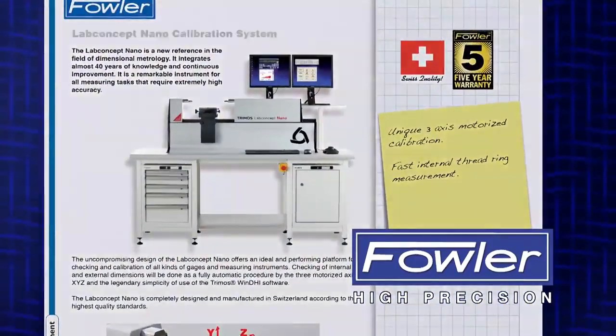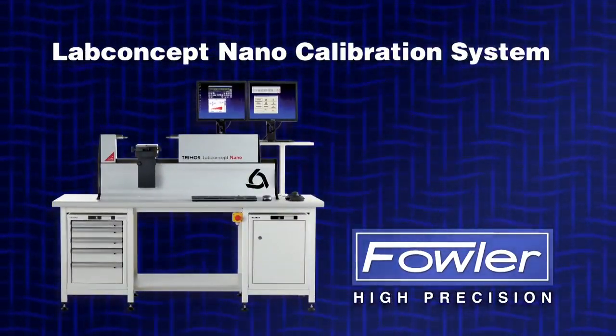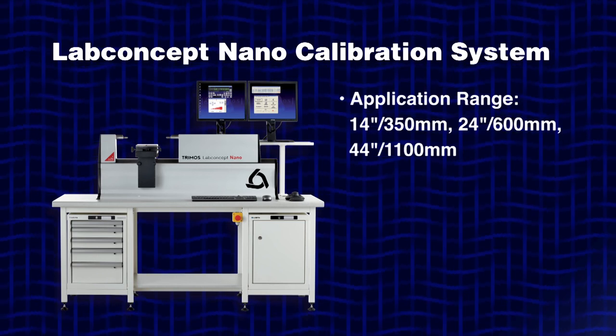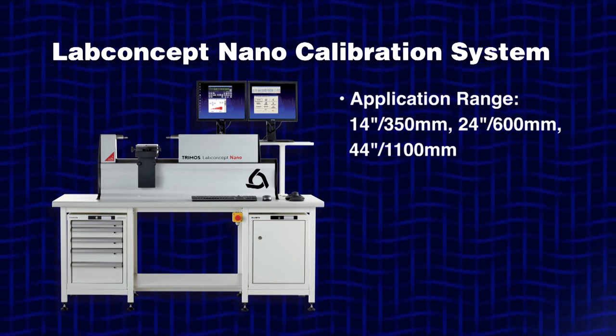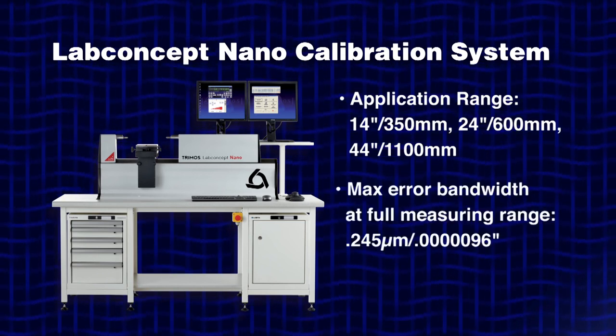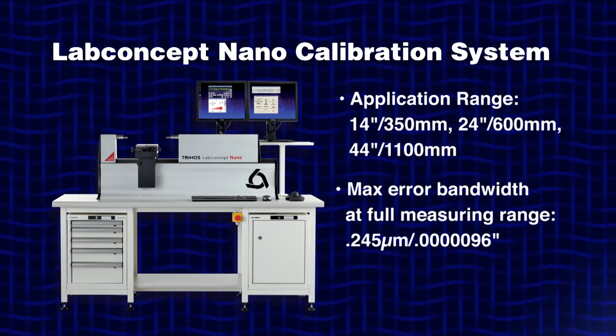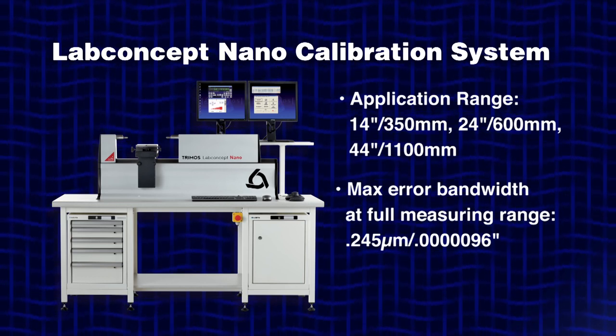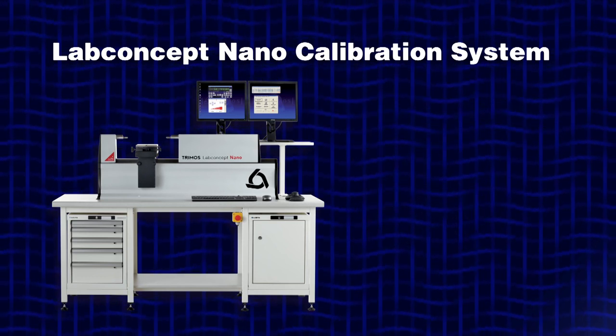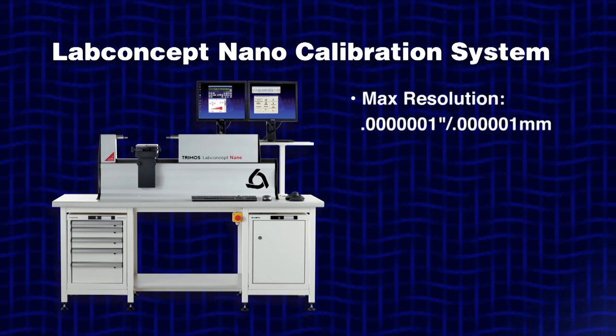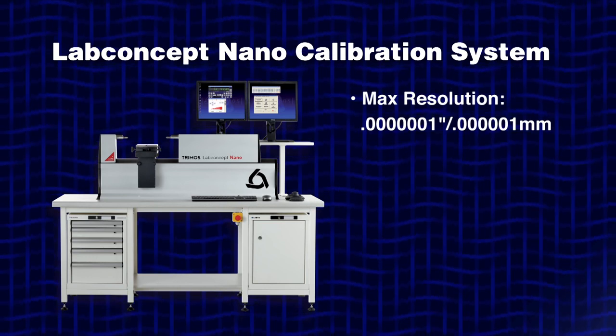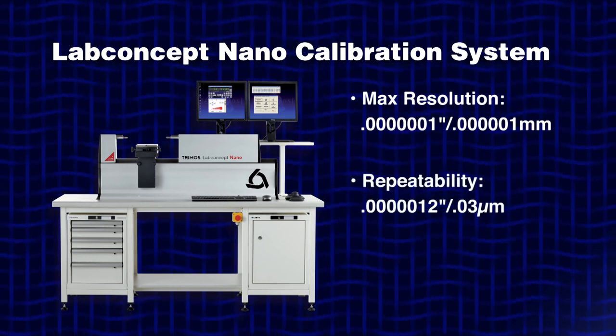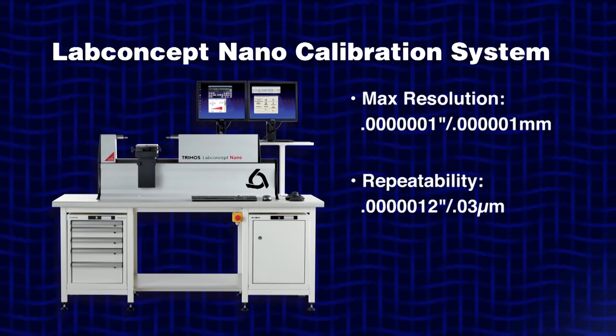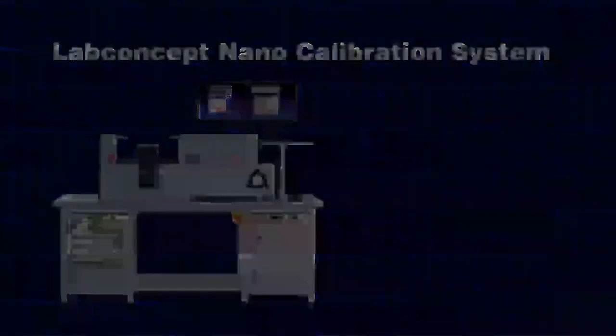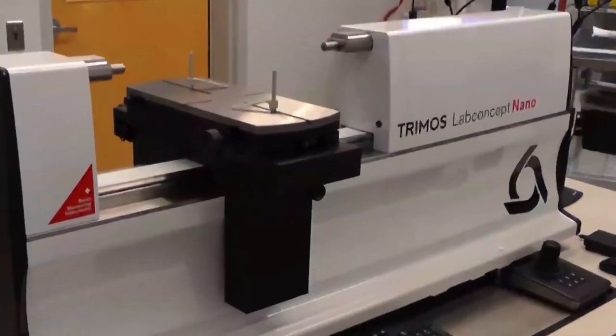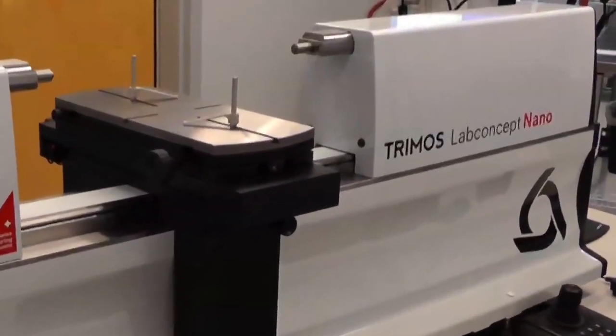The Fowler-Trimos Labconcept Nano is our most accurate gauge to date. It features 3 application ranges, 14-inch, 24-inch, and 44-inch, and a max error at full measuring range of 0.245 microns, or 9.6 microinches. The Nano's resolution is 0.1 microinches, or 1 nanometer, and is repeatable to 0.03 microns, or 1.2 microinches. In this video, we will outline some of the most common measuring applications.